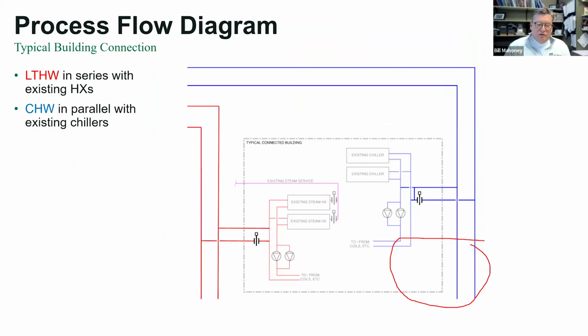But to delve into one of the typical buildings, we were serving buildings that were either standalone. They almost all had steam heat exchangers from a steam source here, but if they did have cooling, they had chillers in the building, or it was a mini district or something like that. So where there was a mini district, we just went to the building that distributed chilled water to those 3 or 4 buildings around it, and we just tied in like a parallel chiller here, and just treated it like building pumps. We delivered distribution pumps, delivered the water to the building edge, and then we have a deny valve, and we tie in just like you would tie in a satellite plant or something.